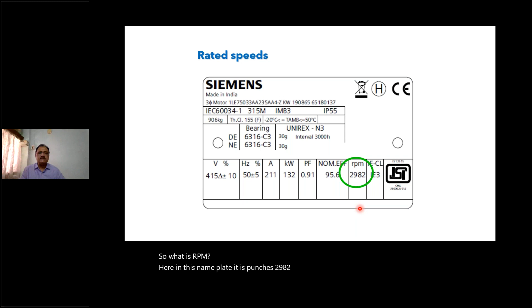My aim in spending a little extra time with you is that you have to understand these parameters of the motor, so that when you see these motors in the field, either after getting employment or on an industrial visit, you will appreciate that these are the reasons why these RPMs are chosen. So what is RPM? Here in this nameplate, it is punched as 2982 RPM, which is a 2-pole motor, right? So what does this mean?